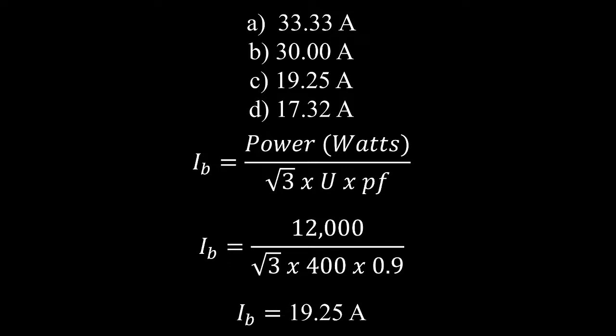There could be other factors as well there, Sam, couldn't there? We did it as a straightforward calculation, but not taking account of installation methods or even the type of motor, because if it was a motor that was stopping and starting, as in a compressor in a motor vehicle workshop, then you'd have to add other factors to help calculate the load, or add a rule of thumb factor for the added inrush current on startup. But this was done purely as a desktop calculation, wasn't it? Yes, and it was really just to emphasise that I think the person who asked the question originally forgot about the √3 factor, which obviously resulted in a much different current. So one of the things we wanted to bring out is to be aware, when we're working with three-phase, that we have to consider that root 3 factor when we're looking at the individual phase currents.